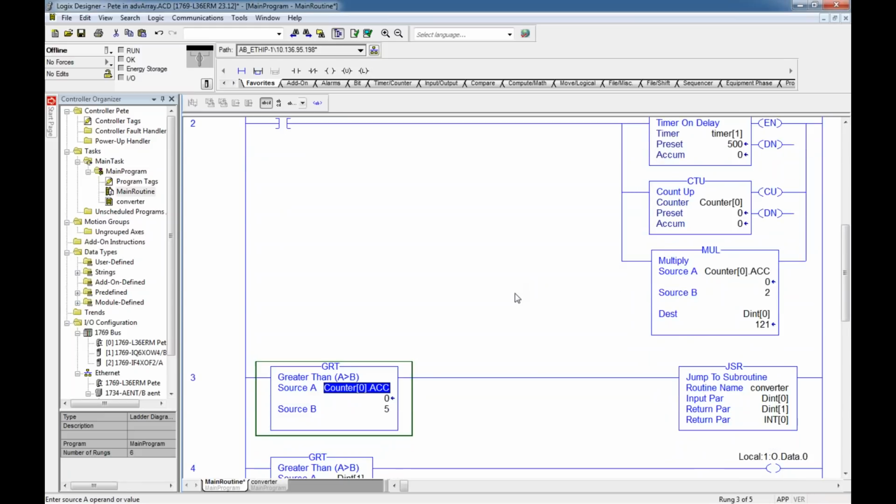Just beware when you use an equal. Make sure you're using dints and not reals, because with real, there's going to be so little. You're never going to get exactly on because of the decimal and rounding with real float value numbers. So it will never come on if you're using real. It's better maybe to use a small limit if you want to use a real, but never use exactly equal. And if you have a process that's going really fast, equal is going to be on for a second. You may want to use a range of limits to give yourself some leeway.